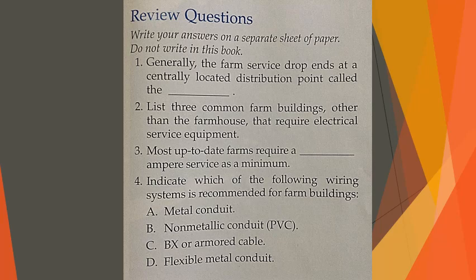There may be others. Question 3, fill in the blank. Most up-to-date farms require a blank ampere service as a minimum, and that is 200. It can range from 200 to 400 and up. Question 4, indicate which of the following wiring systems is recommended for farm buildings. The answer is B, non-metallic conduit or PVC. You should avoid all kinds of metallic equipment or conduit.